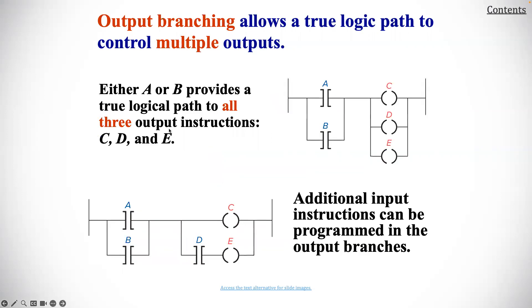Output branching allows a true logic path to control multiple outputs. Either A or B provides a true logic path to all three output instructions: C, D, and E. Additional input instructions can be programmed in the output branches.